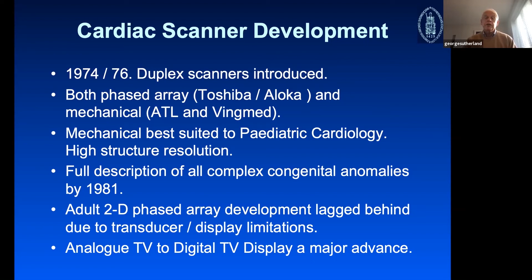It took some time to correctly manufacture the ceramic probes and mount the crystals. And a major problem of the initial crystal ultrasound development of 2D was that it became very difficult to solder the leads onto the crystals and get the information out of the scanner head into the system. But by the mid-1980s, we had a vast selection of things ultrasound could do. In terms of linear arrays, they are used for non-moving objects, and they're used obviously in obstetrics, in abdominal scanning, in head scanning. Cardiology requires sector scanning, and the sector scans went from 56 to 128. You have an enormous amount of crystals you could pack onto a transducer head.